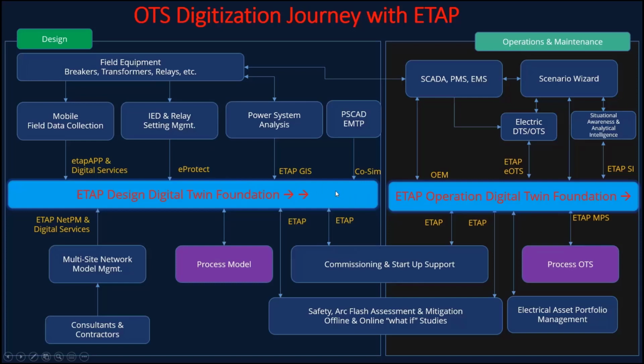Eventually, once the digital twin is tested and validated, it goes into operational digital twin convergence, connecting to your existing SCADA, PMS, or EMS system, or ETAP itself becomes the SCADA, PMS, and EMS, getting all the real-time data from field equipment like generators, meters, relays, breakers, and loads. All the real-time sensor data available in the SCADA or PMS gets transferred to ETAP, and the same model that came from the design basis converts into an operational digital twin model as an electrical DTS, dispatcher training simulator, or operator training simulator.